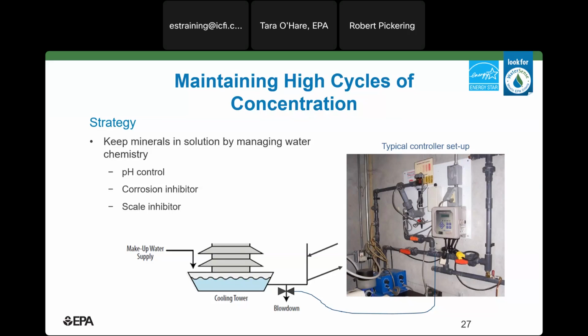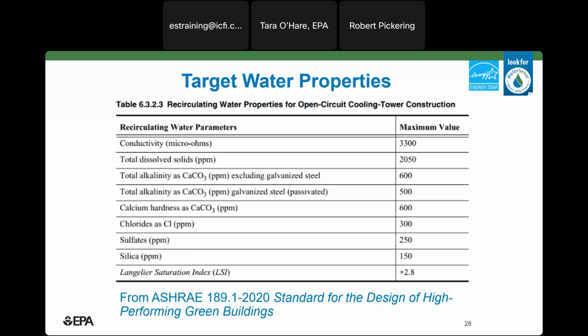To maintain high cycles of concentration, you can keep minerals in solution by managing the system water chemistry. Minerals are kept in solution by adding chemicals or another treatment mechanism that can control the pH and inhibit scale and corrosion. The target cycles of concentration that is achievable in your cooling tower is based primarily on your facility's incoming water quality. This table is from ASHRAE 189.1, which establishes maximum values for certain parameters that recirculating cooling water should stay below.